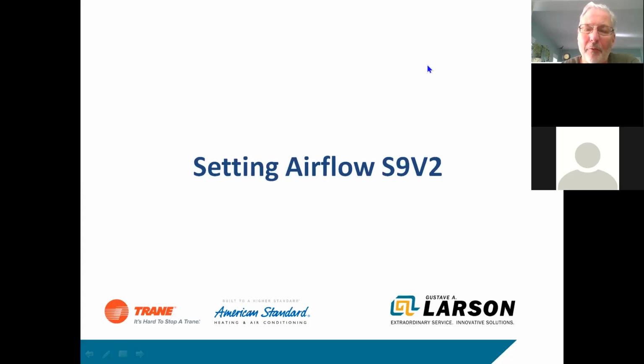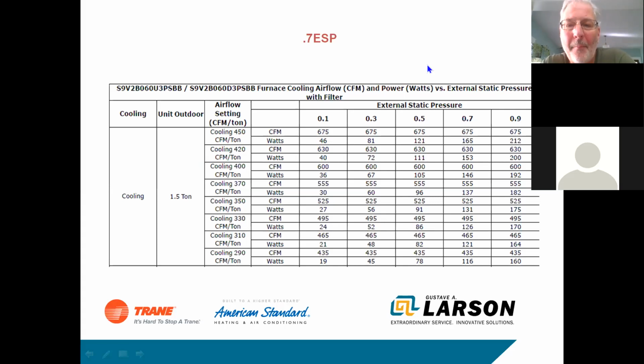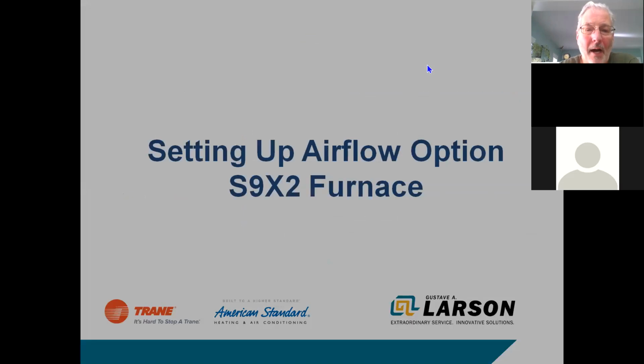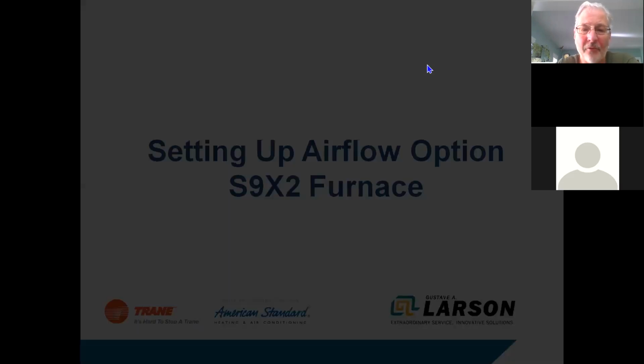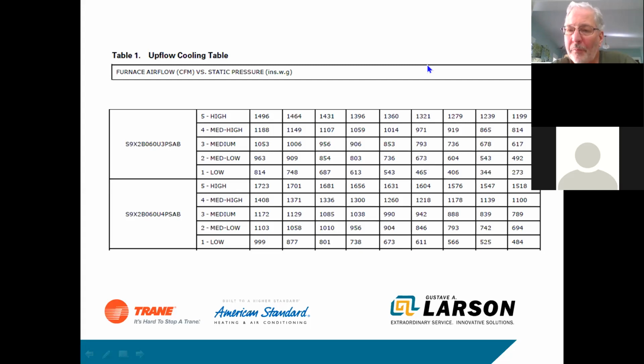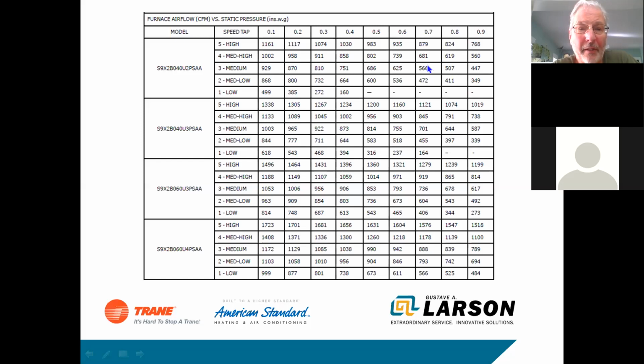But setting the airflow on the S9Vs, one of the things that you'll find on the S9V furnaces is that you can fine tune it pretty easily. I mean, you can set the tonnage, you can set the CFM per ton, and the furnace will dial itself in. And if you look at the blower curve, it'll move the right amount of air, based on what you're set for. On the S9Xs and the S8Xs, it's a little different. We have some 5-speed motors out there, and we have some 9-speed motors out there, okay?